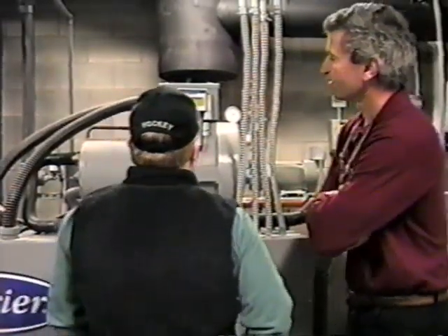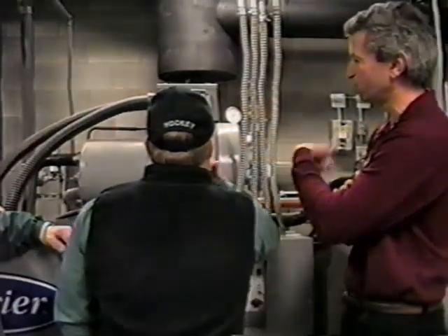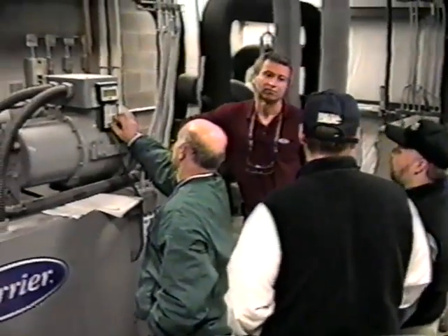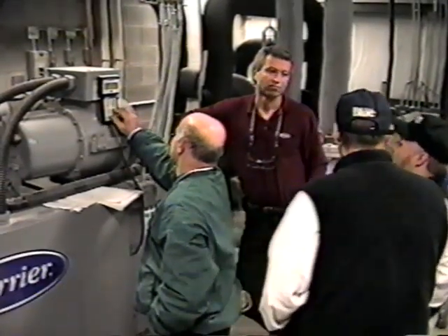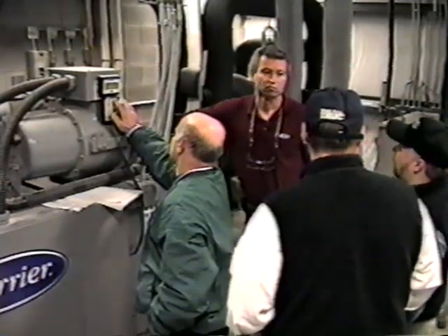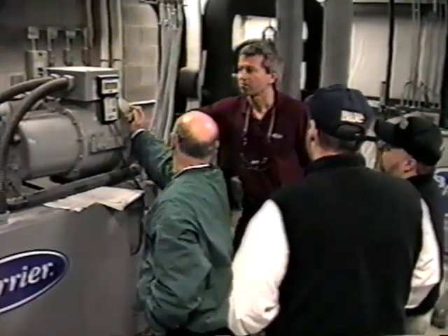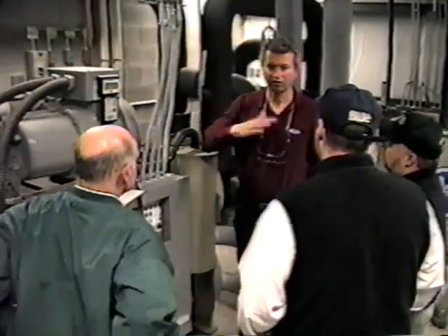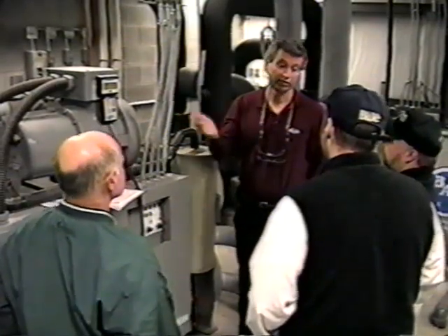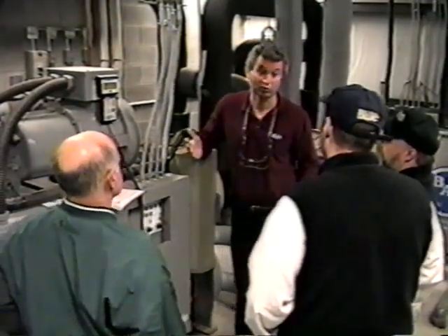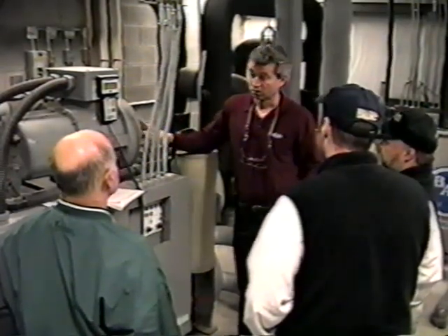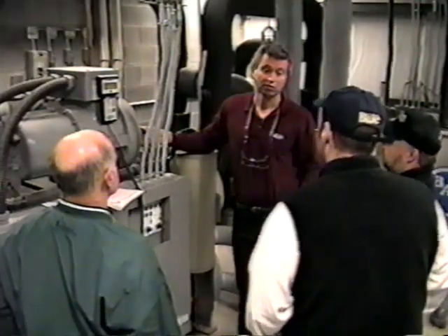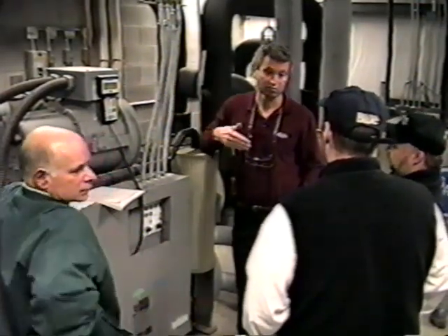Let's say I wanted to go back to the default screen. How would I get there where it scrolls? Automatically sequence on. Will it bang on all at once? No. So is that what that blinking was, the 15 degree set point? Yes, that's what it currently is. Because we don't have complete variable control, it's kind of step control. There is a deadband there. It may drop to 14 or 13 and a half before it ultimately shuts off. But at that point, whatever compressor is running is going to be fully unloaded. Okay, so it'll try to back off and stay running before it shuts you down.